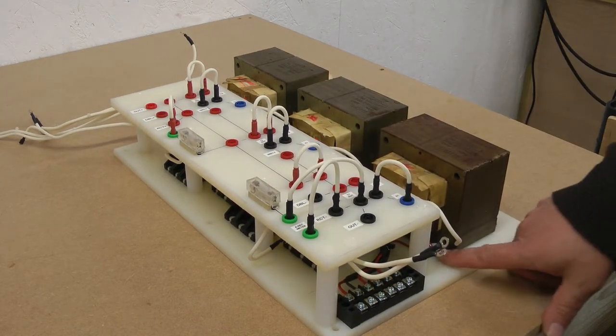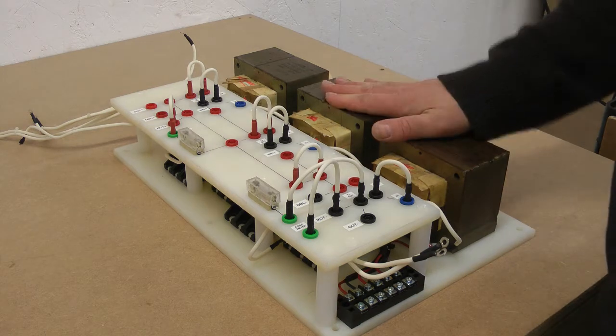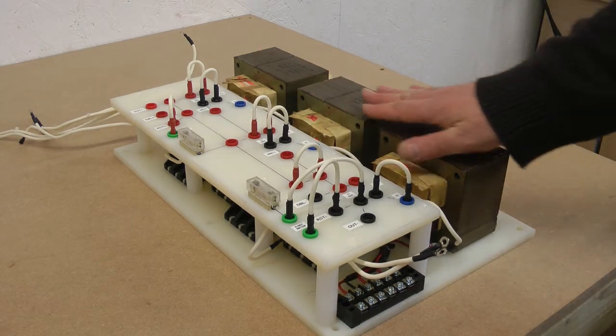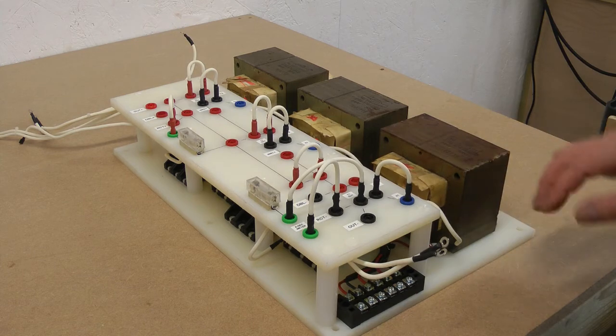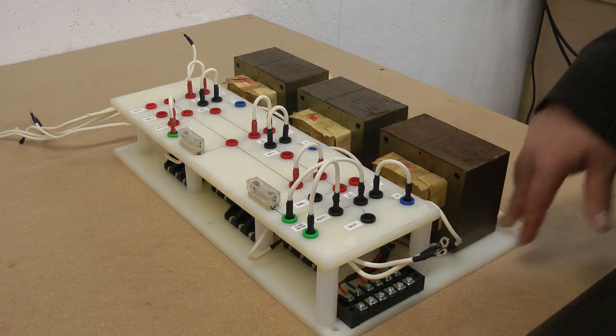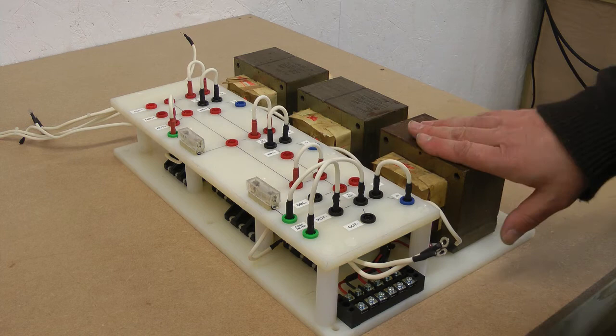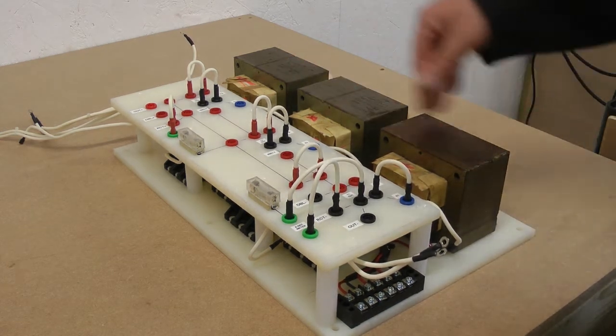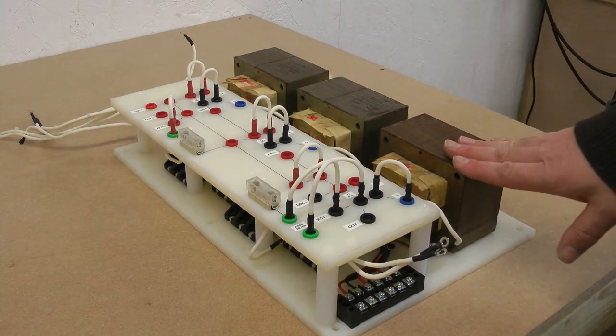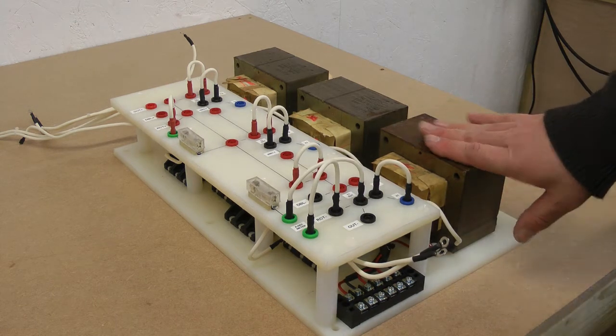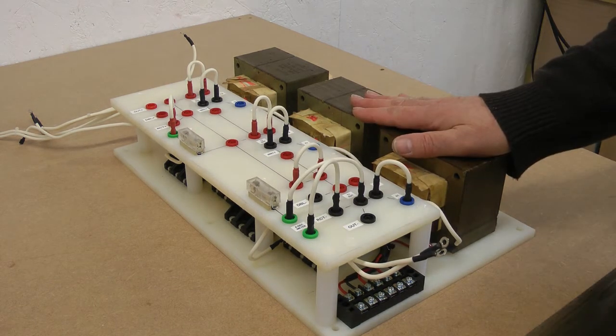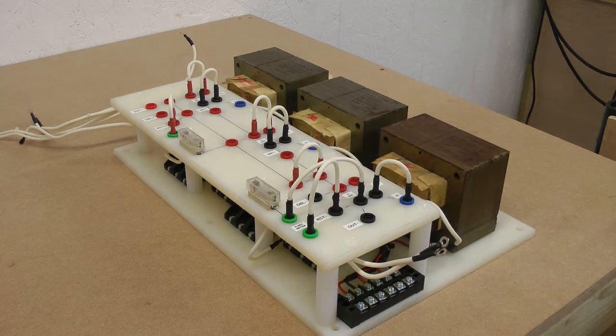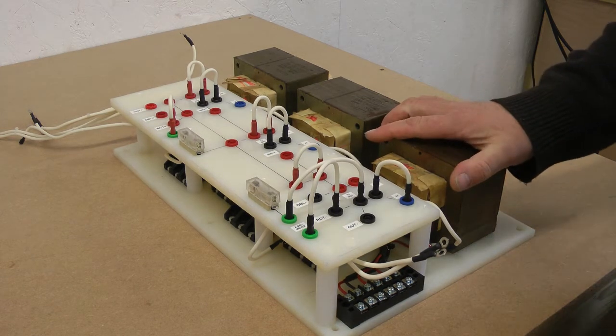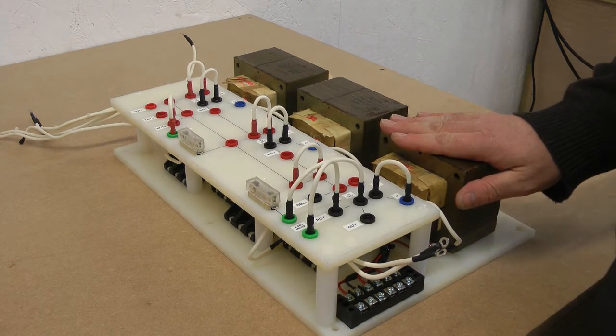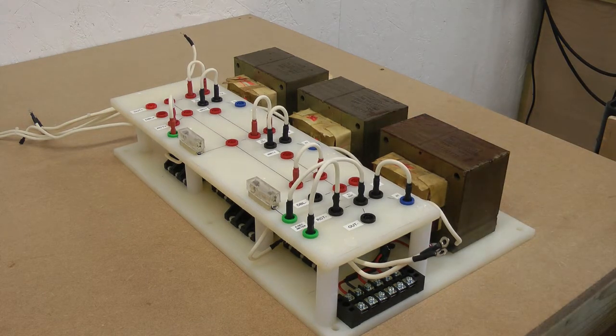They are all mounted down with nylon bolts. So again, we are cognizant of how everything is mounted together in terms of the high voltage isolation. Remember, we might be running this with a total potential across those transformers open circuit at 9 kilovolts. 9 kilovolts is a hefty potential. It's about, in air, about 30 kilovolts per centimetre, so at 9 kilovolts we're talking about 3 or so millimetres that the potential could jump.